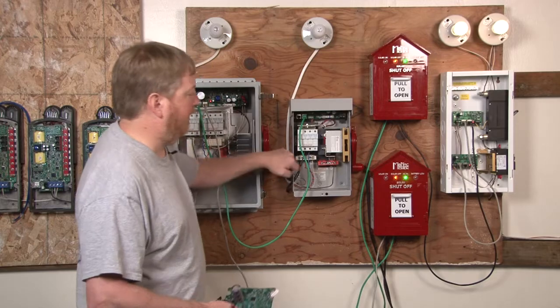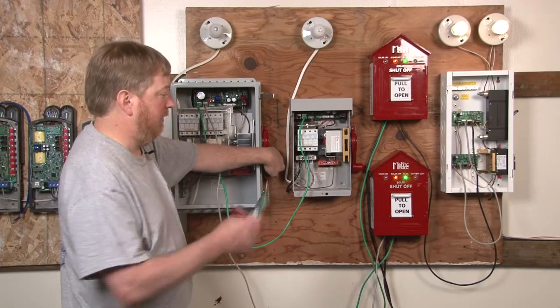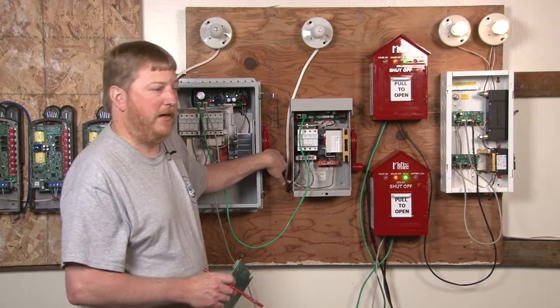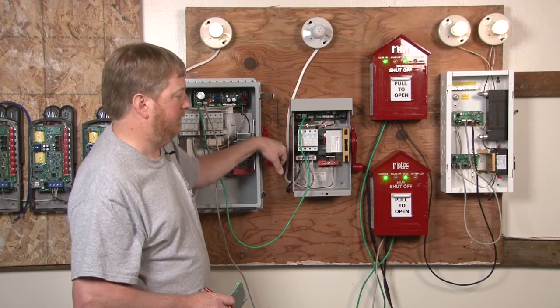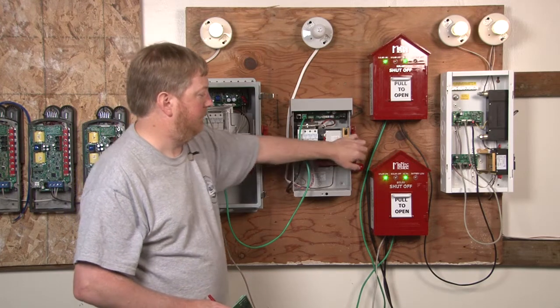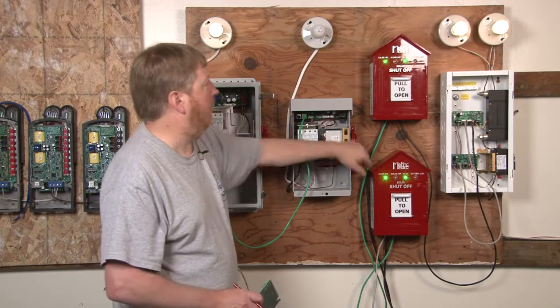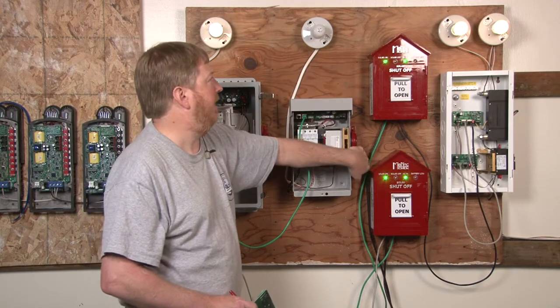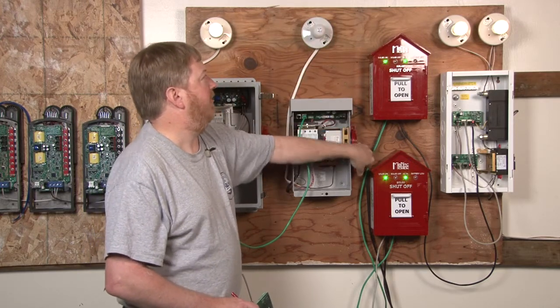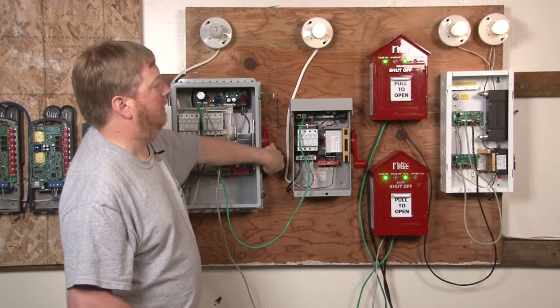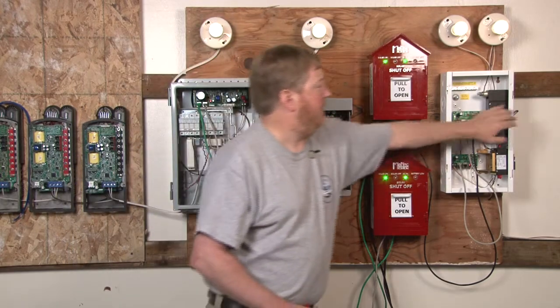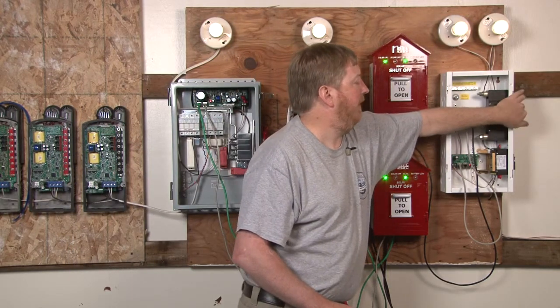I'm going to turn the combiner box back on, and the birdhouse is going to tell us the combiner box is now back on. The combiner circuit breaker is closed. I also wanted to point out that you notice each light bulb works independently. So as you can see, they're all independent at the moment. Battery disconnect module, again, independent lights.